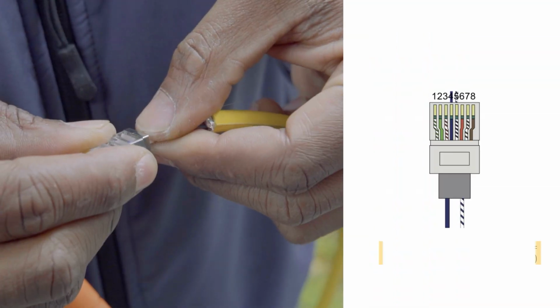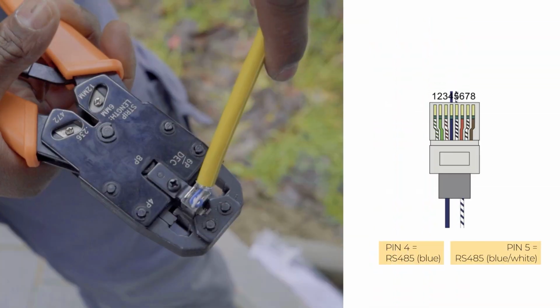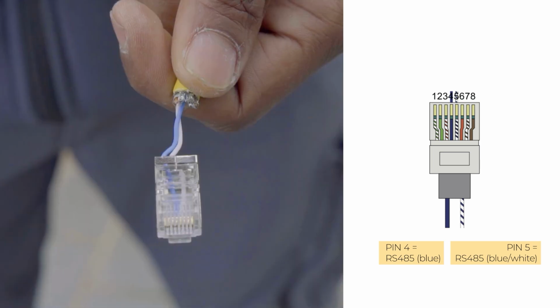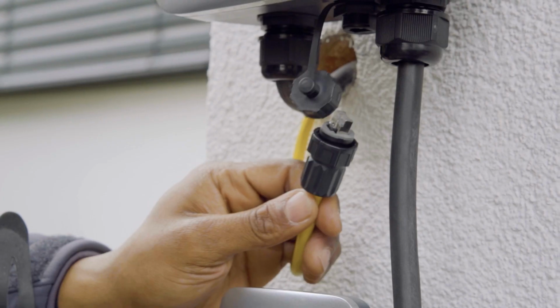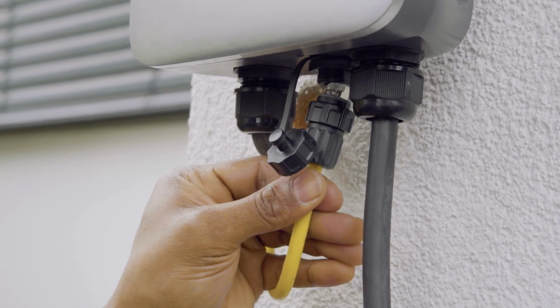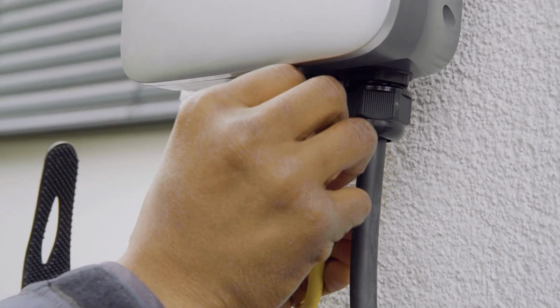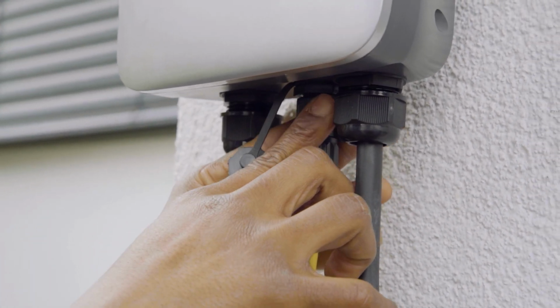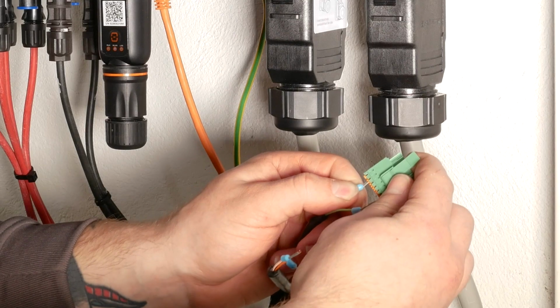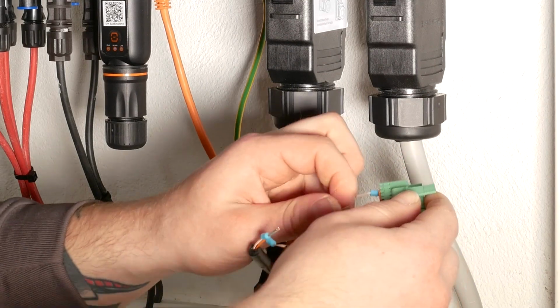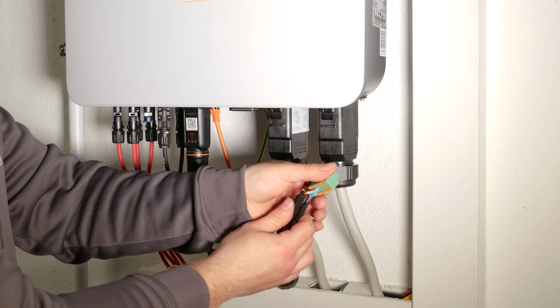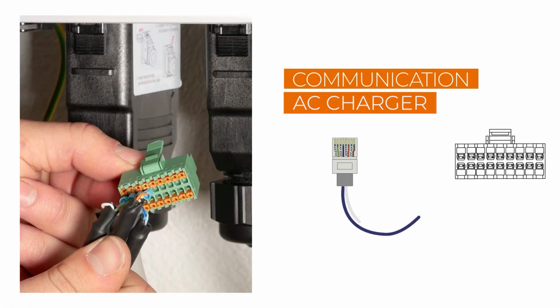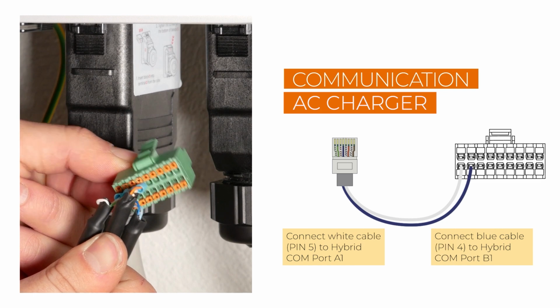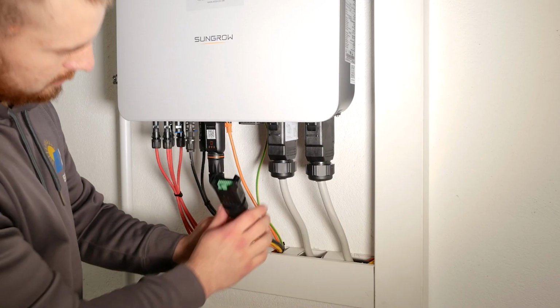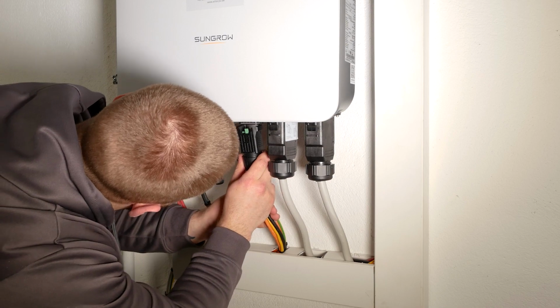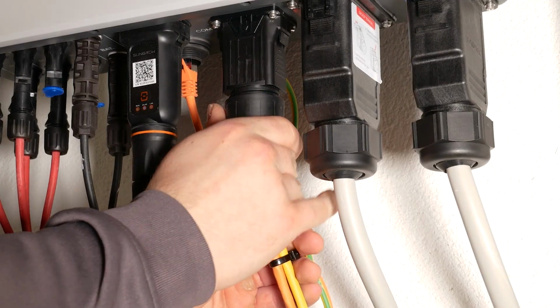Use the enclosed cable gland to connect the communication cable with the AC charger. To do this, insert the Ethernet cable through the gland at the bottom of the box and plug it into the charger. Tighten the cable gland on the AC charger. Use the other end of the cable to connect it to the hybrid inverter. Disconnect the communication connector and insert the RS485 cable. Connect both RS485 communication wires to the communication ports A1 and B1 and plug it in. Now the AC charger and hybrid inverter are ready to communicate.